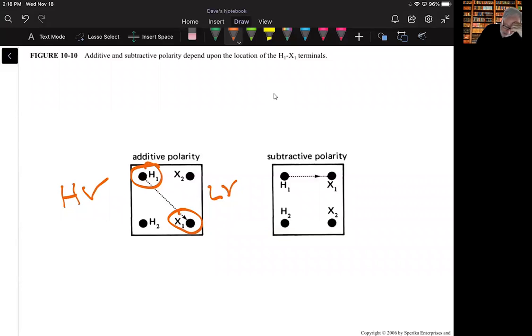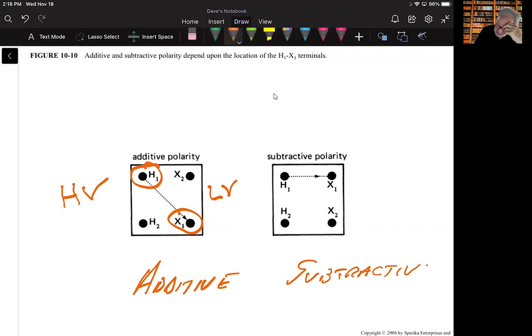Although the polarity is known when the symbols are given, in the case of power transformers it is common practice to mount the 4 terminals on the transformer tank in a standard way, so that the transformer is determined to be either additive or subtractive, okay? That's another electrical thing that we need to know. It would be a question you would ask: is this additive polarity or subtractive polarity?